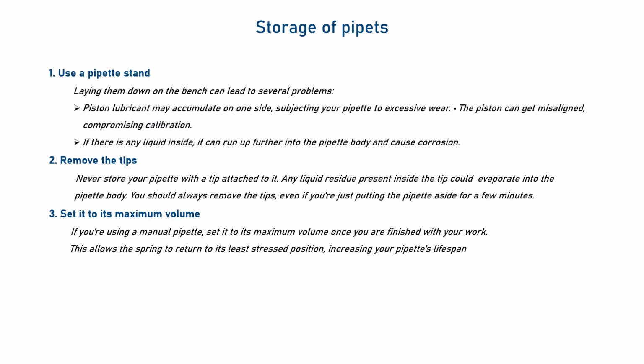Here we have a few things to keep in mind whenever we are not using our pipette and storing it. The first point is to use a pipette stand and store our pipettes vertically. Whenever we just leave them on our bench in a horizontal position, the inner workings of the pipette can get misaligned, which would void your calibration. Second point is to always remove the tips. Any liquid which remains in the tip will evaporate in time and get into the pipette itself. And again, this can cause troubles for the inner workings of the pipette.